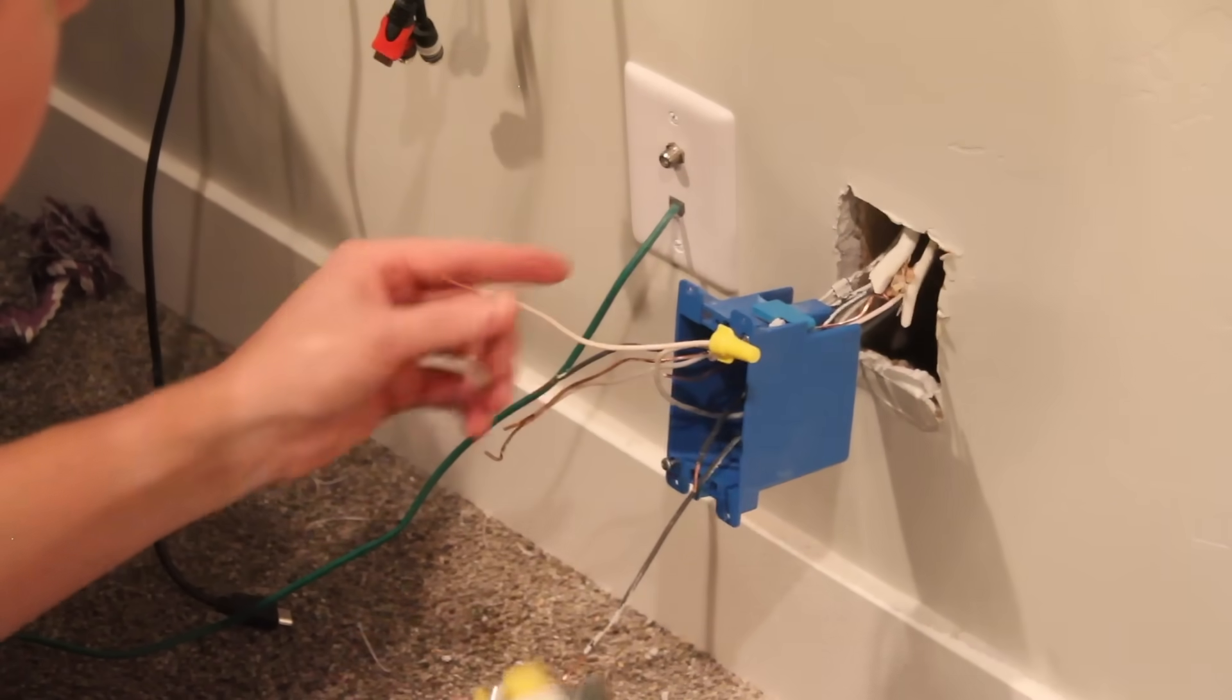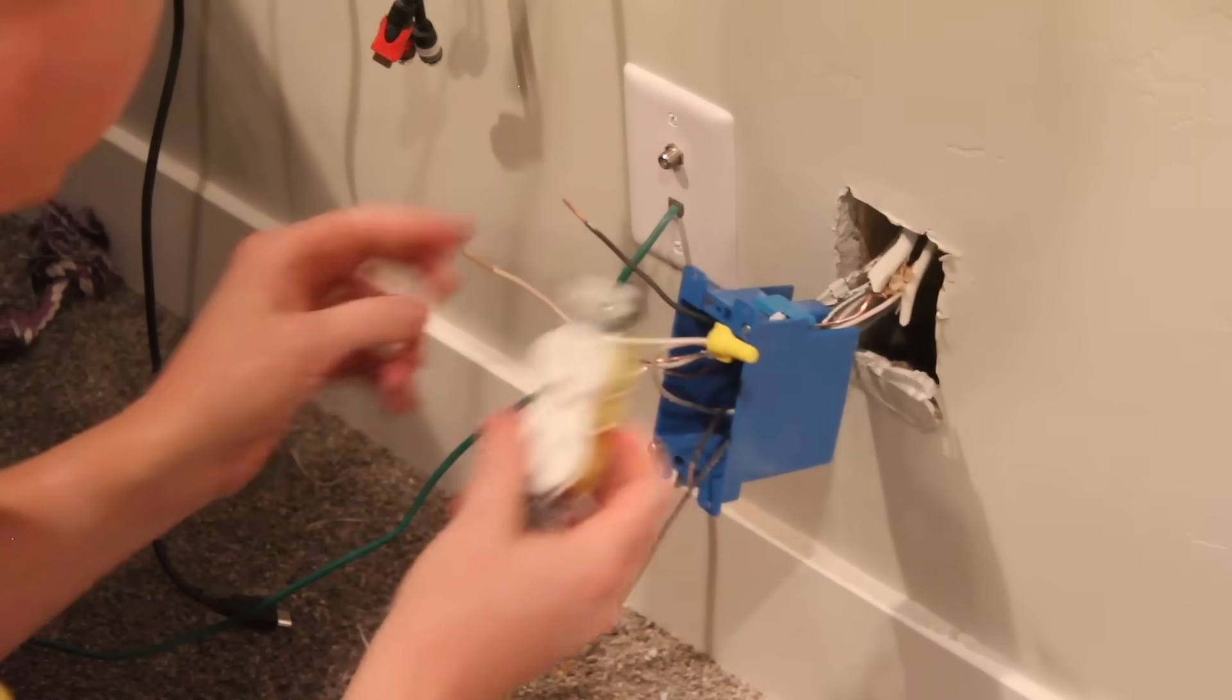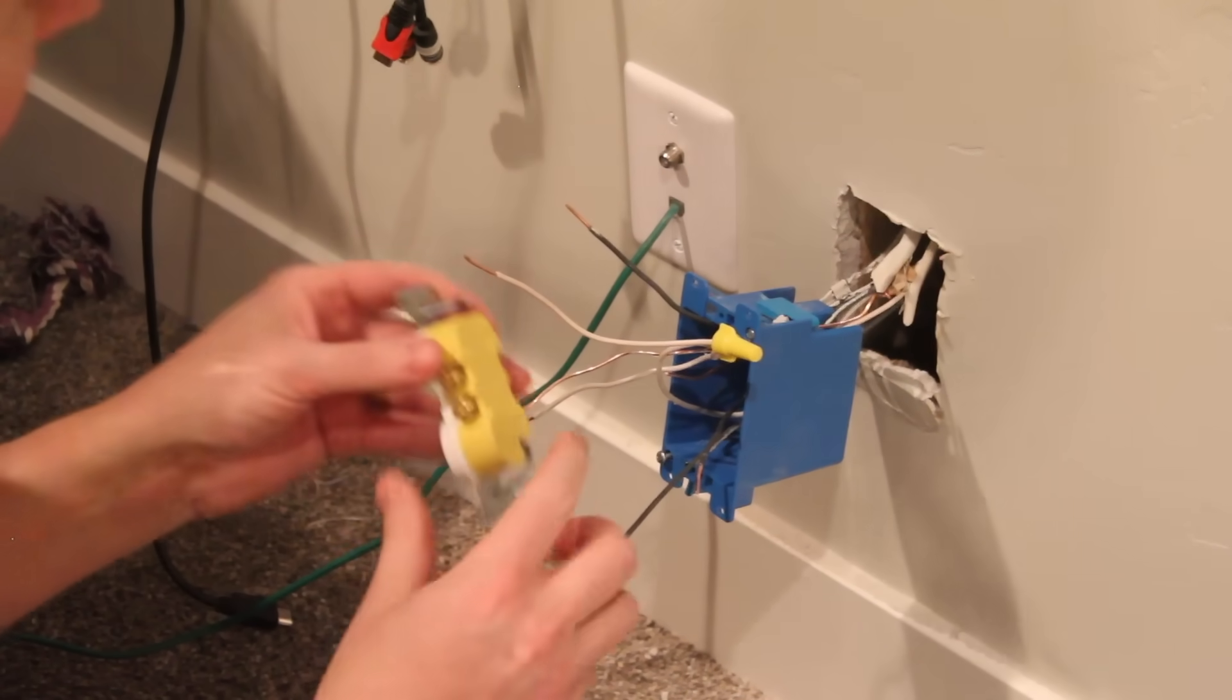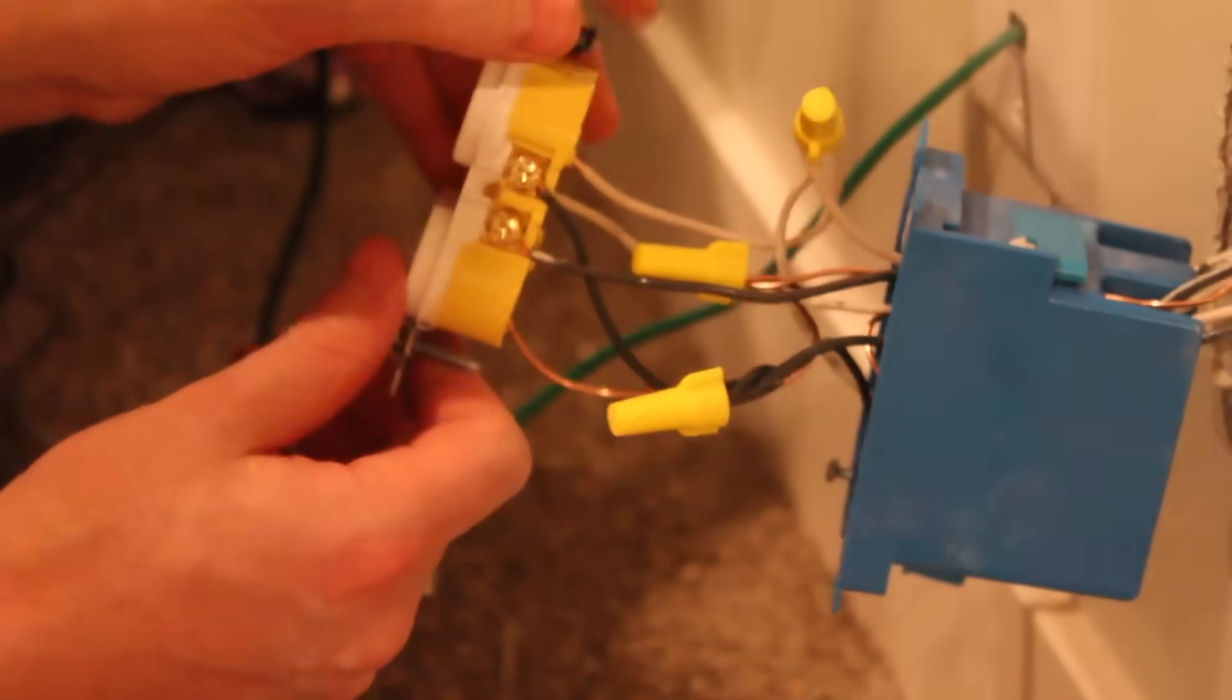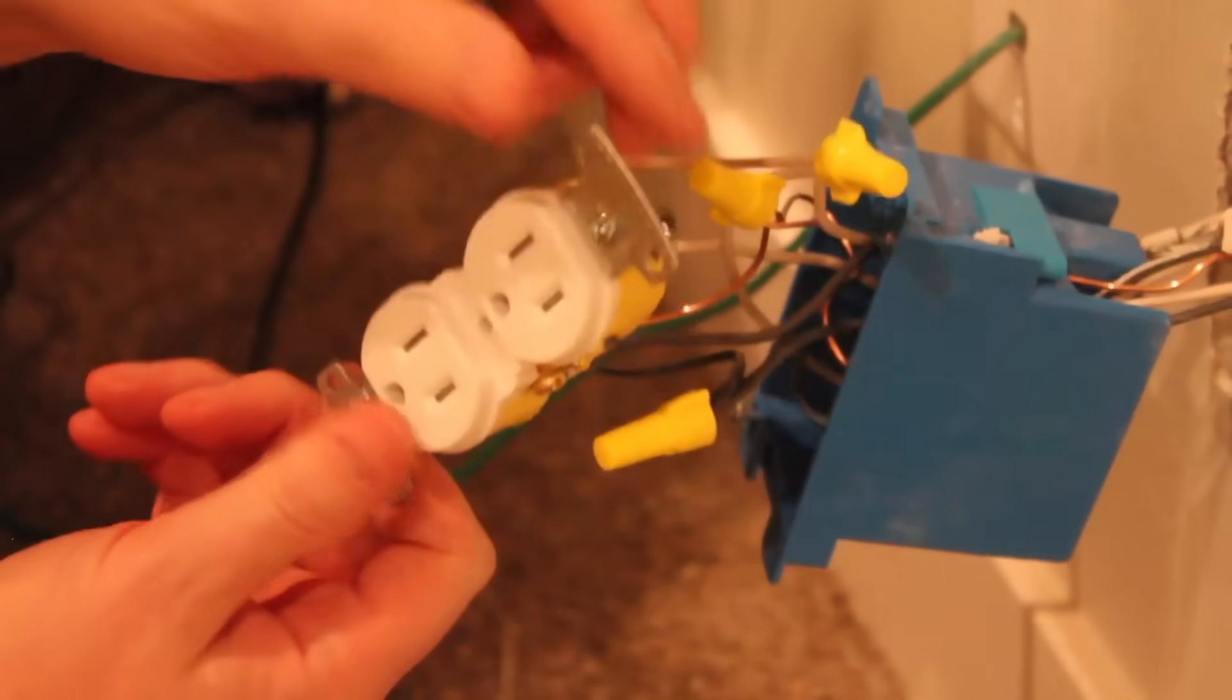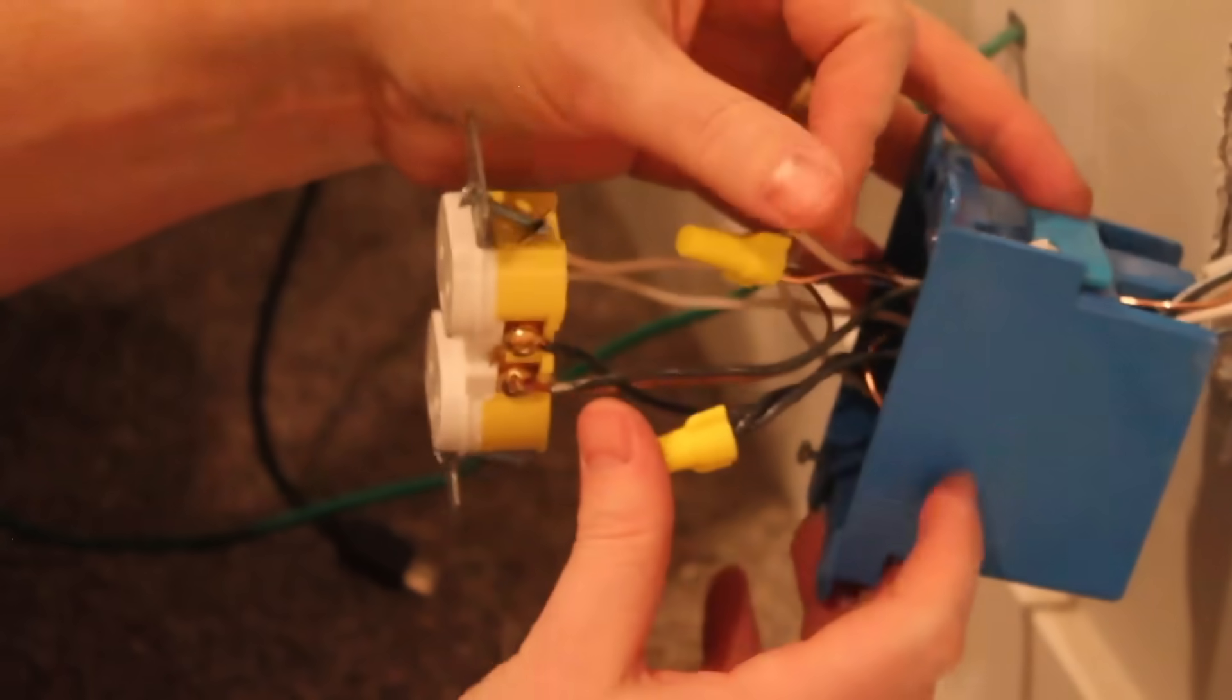And then we're going to slip a cap on and tighten it down real good to make sure that the connection is solid between all three of these. What that leaves us with is just one to put into the actual outlet itself. What you need to remember is that black goes on brass. You've got your brass side and your silver side. So black goes on brass, white goes on silver, and then your ground goes on green. Your bare ground goes on green. So we're going to wire this back up kind of like we had it before. We're just not going to use the holes in the back to do that.